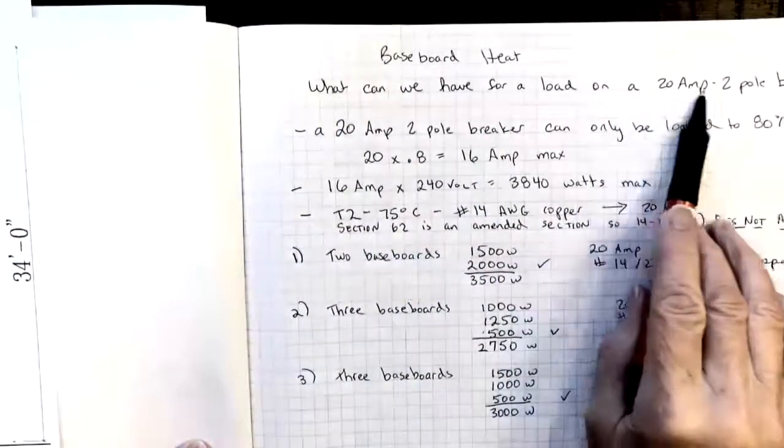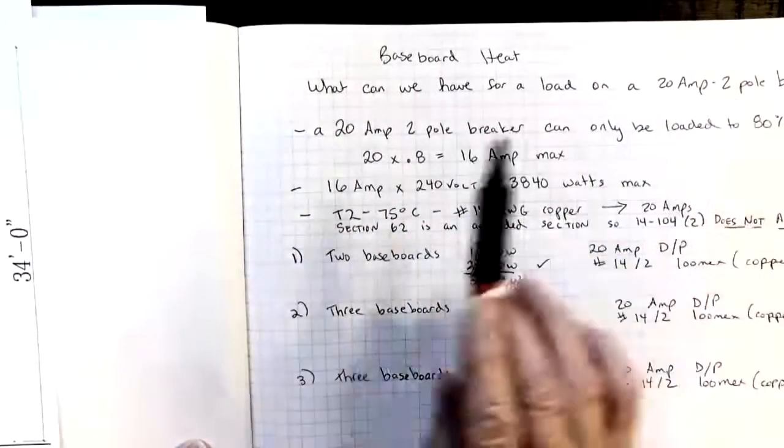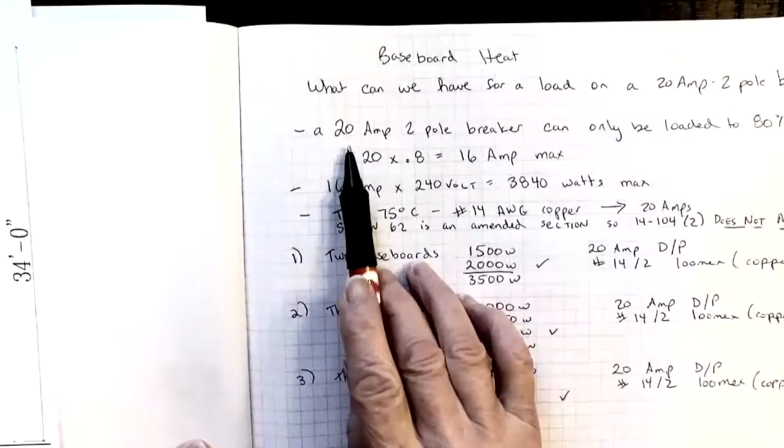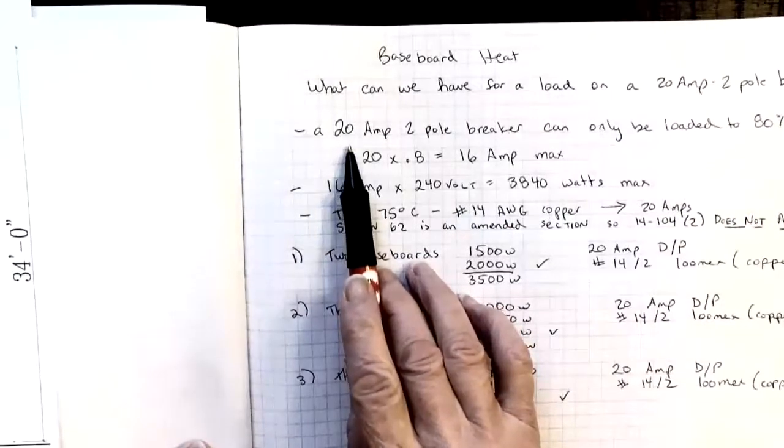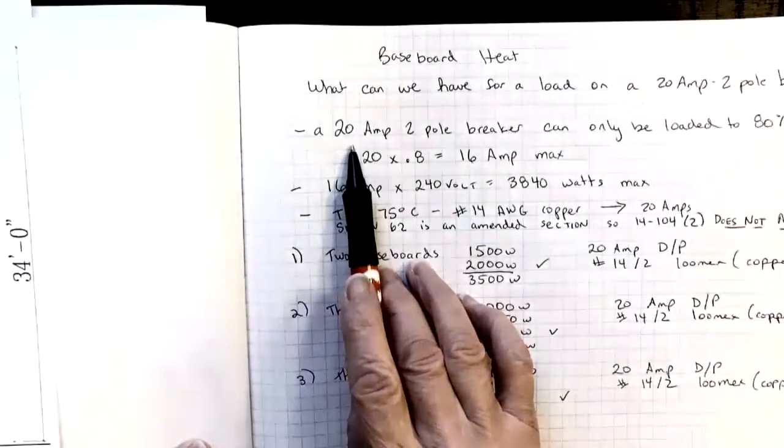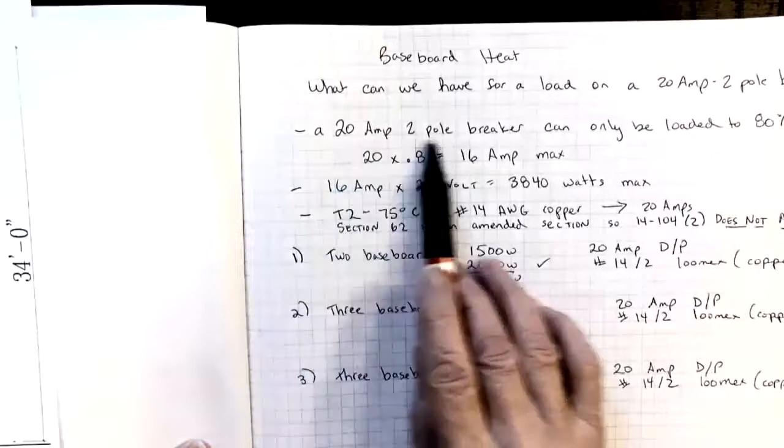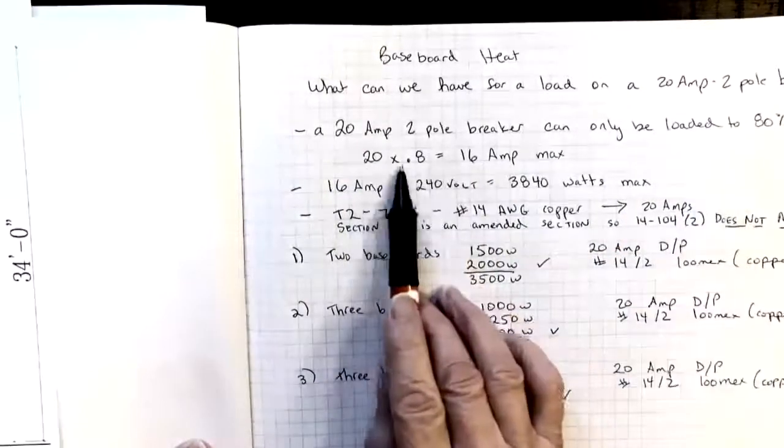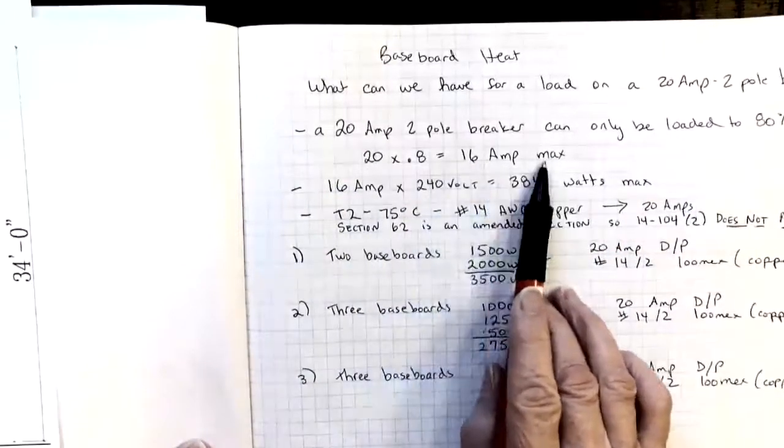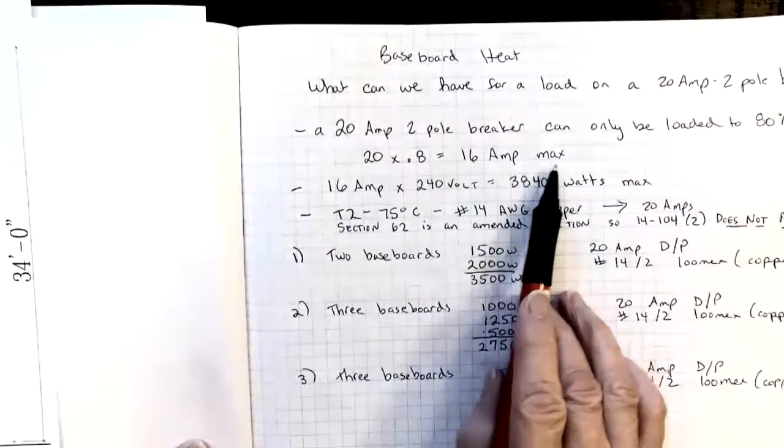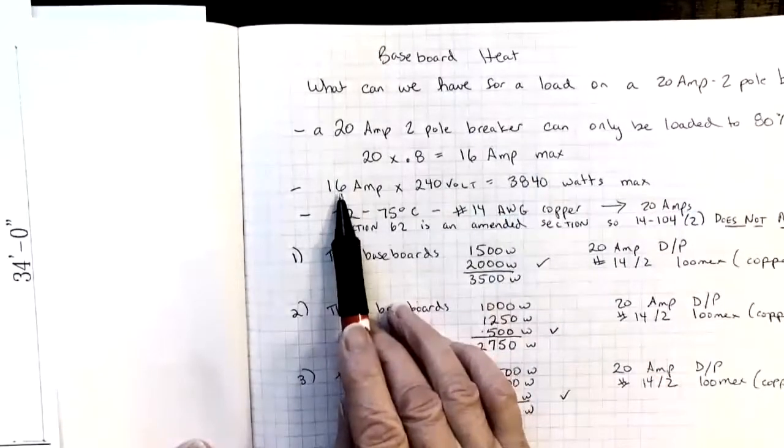So a 20 amp two-pole breaker, when we look at how much we can load it up to, previously we saw a rule in section 62 that said we could only load this 20 amp breaker up to 80%. 20 times 0.8 gives us 16 amps max on that breaker.